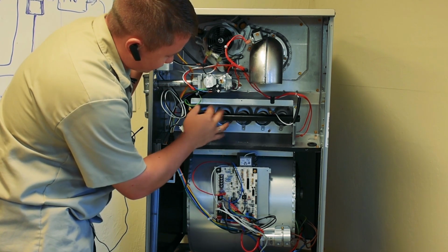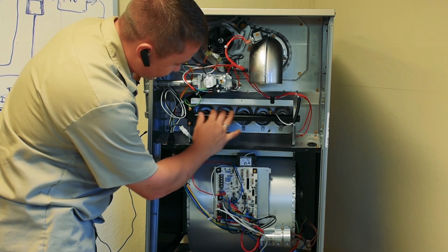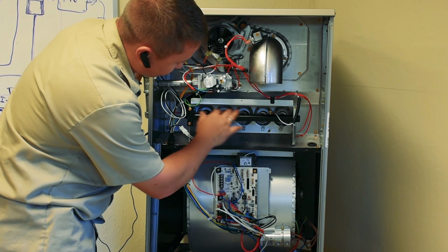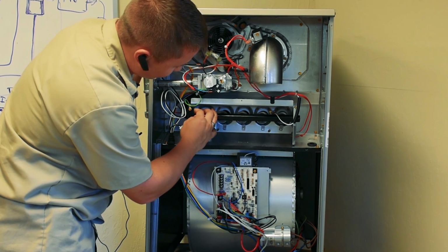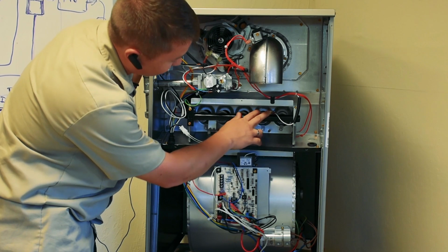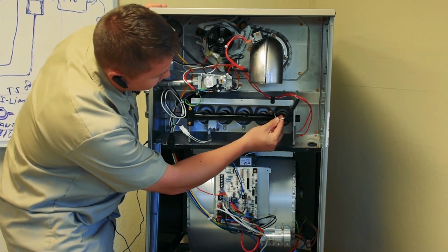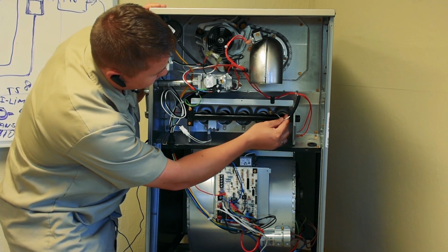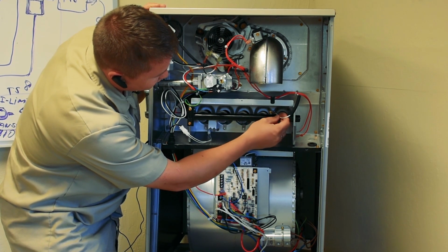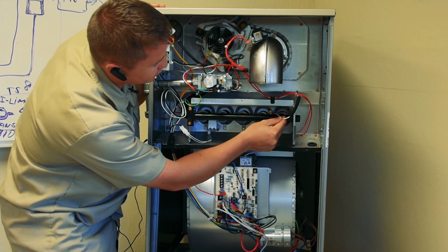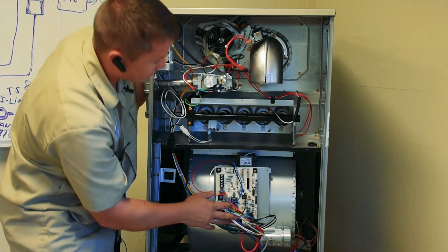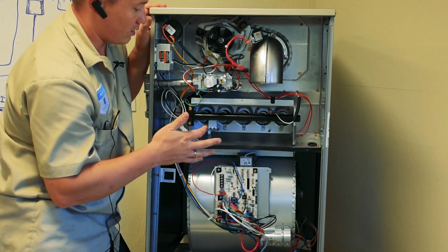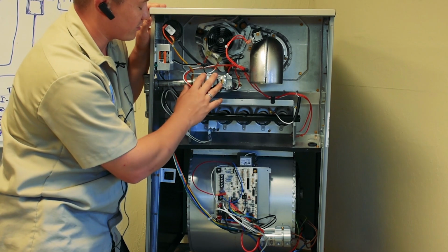Alright, then because the gas is running to the gas injectors, and your igniter is already ignited, red and hot, the gas will get a flame. This will be a very high temperature flame, and here this wire is actually a flame sensor. This flame sensor sends a small amperage electricity to the control board, and it tells the control board to keep the gas valve running.